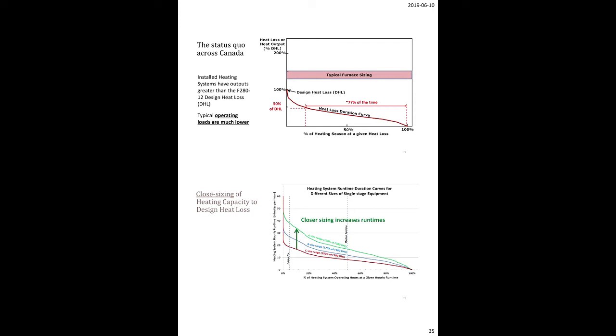This is really sort of odd, but it's the reality. So we know the status quo is we have to get closer to designing. We need to do our loads. We need to understand them. We need to measure them and design appropriately. We know that the equipment we put in is most likely going to run at part load for the vast majority of the year, so we need systems that can be variable in their operation with good turn-down ratios, is the old term.